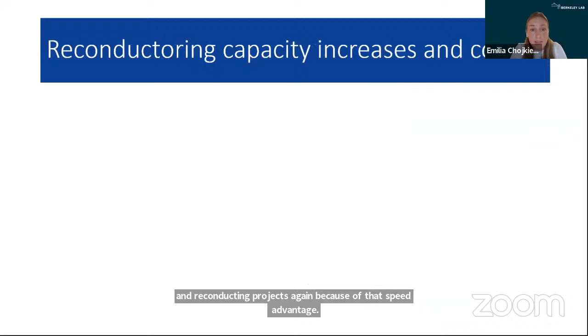The capacity increase obtained through reconductoring usually depends on the line's limiting factor, which is generally a function of the line length. Short transmission lines are generally limited by thermal limits, while long lines are constrained usually by voltage or stability limits. What we found is that 98% of existing transmission lines are actually short, under 50 miles, and reconductoring with potentially additional reactive compensation, such as voltage support, essentially doubles the thermal limit of the line.